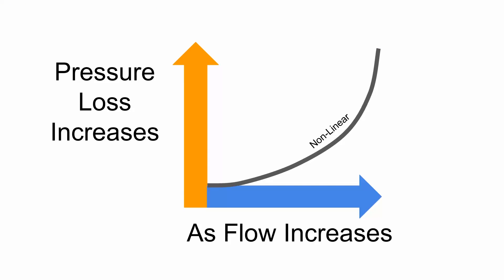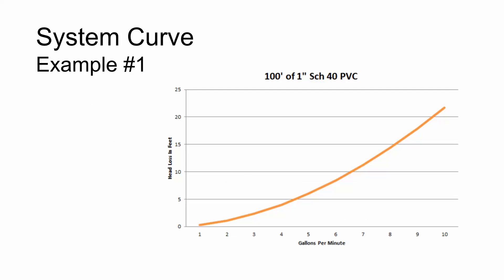Now let's apply that to some real-life information. We've got here a system curve example, and this example is a very basic version of a system curve in that it consists of just a single component: 100 feet of 1-inch schedule 40 PVC pipe, and we can determine by looking at this curve that there is definitely a nonlinear relationship with flow rate and friction loss.